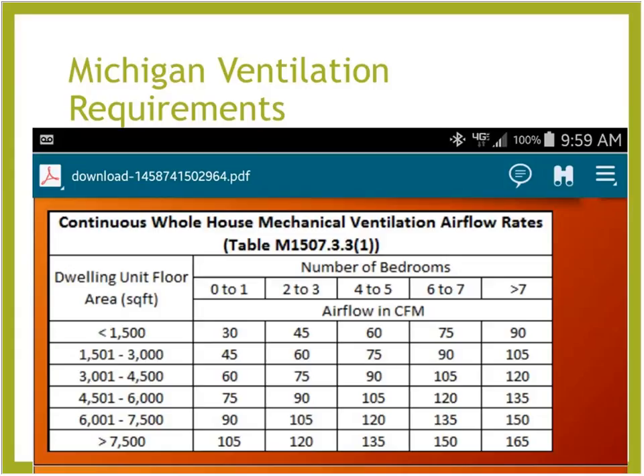Okay. How is that being measured, Mike? I understand with a bathroom fan or a kitchen range hood, you can put a balometer over the bathroom fan or whatever and measure the airflow that way. How are they verifying the fresh air supply system, if you will, that's sucking air into the cold air return? How are they verifying that they're meeting their code requirement with that? Because when we've tested that system in Wisconsin, we've noticed that the CFM actually being drawn in is very, very minimal.